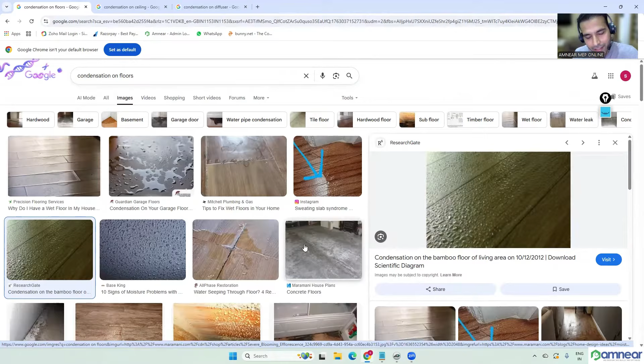Condensation issues can come on the ceiling, the false ceiling. And it can come on air terminals, whether there are grills or diffusers. So what might be the real reason for condensation, and what remedies can we use to mitigate it? That is what we will be discussing in this session. As I said, the condensation issue can come within air conditioned spaces and in non-air conditioned, unconditioned spaces also.